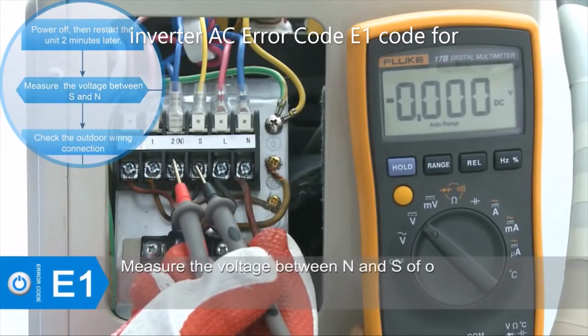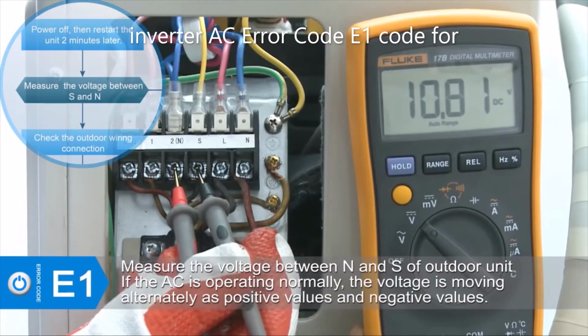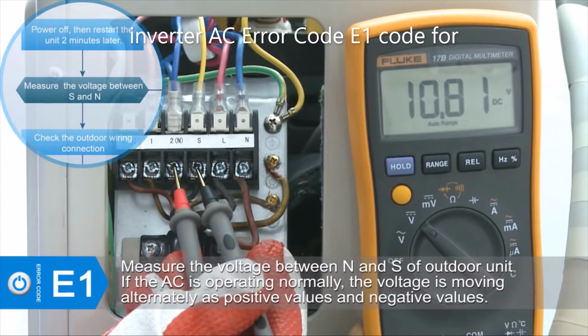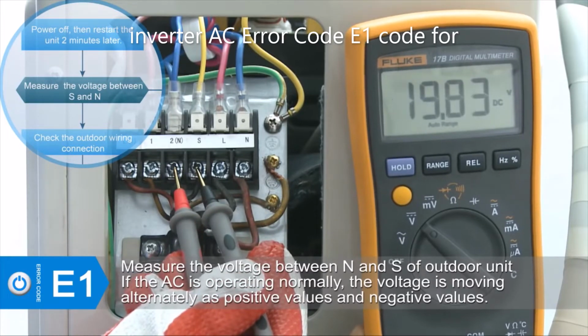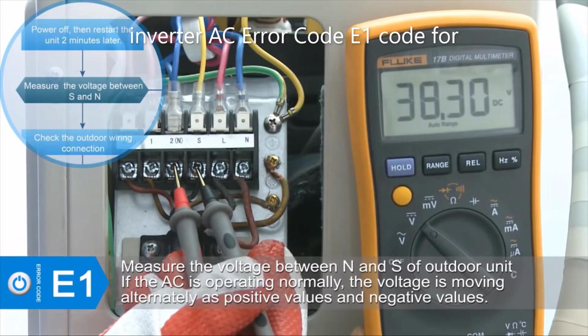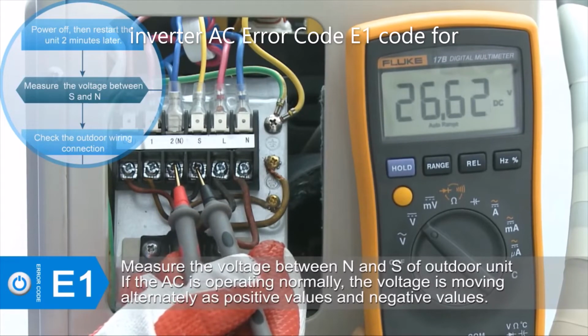Measure the voltage between N and S of outdoor unit. Select voltage DC position, then connect the red pin of multimeter to N port, the black pin to S port. If the AC is operating normally, the voltage is moving alternately as positive values and negative values.